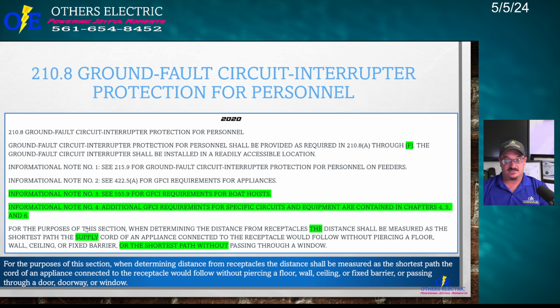This is important because this pertains to us, right? So I want to read this section here. For the purpose of this section, when determining the distance from receptacles, the distance shall be measured as the shortest path the supply cord of an appliance connected to the receptacle would follow without piercing a floor, wall, ceiling, or fixed barrier, or the shortest path without passing through a window.